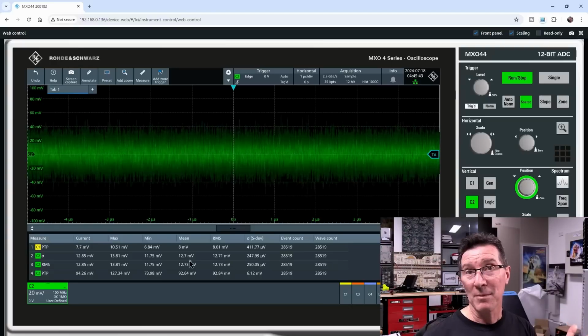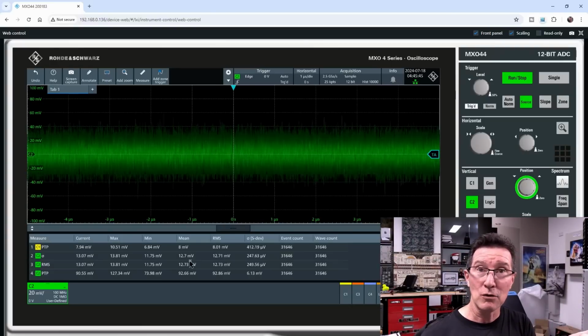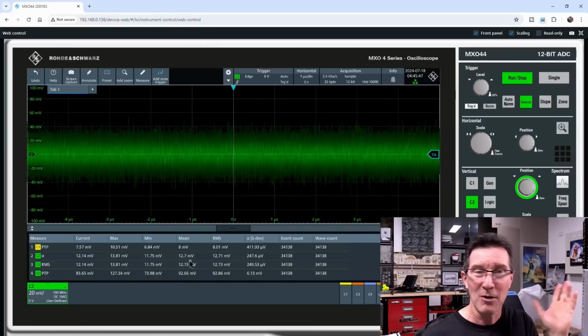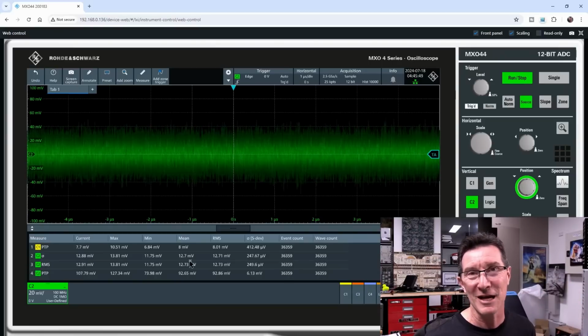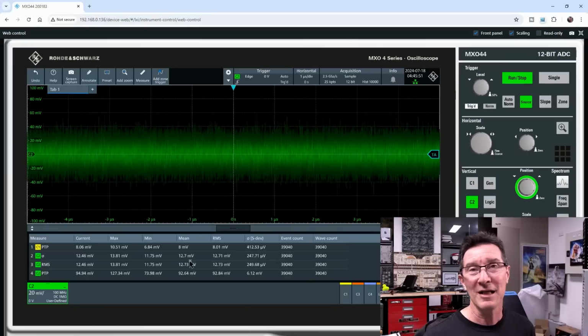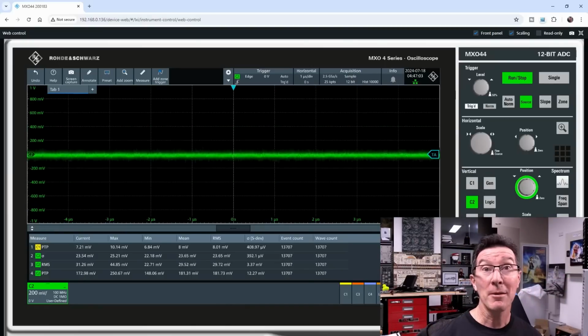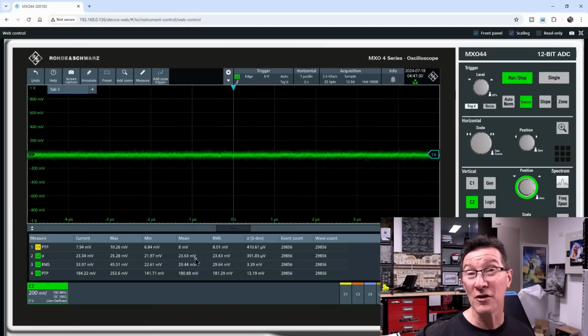And we don't have a 5 megahertz bandwidth limit on the old model. So yeah, I'm just not going to bother cobbling together some external bandwidth limit thing. Doesn't matter. And times 100 mode, reset that. We're looking at 23.6 millivolts. So the previous model was almost half the noise on the higher attenuation setting than this new model.